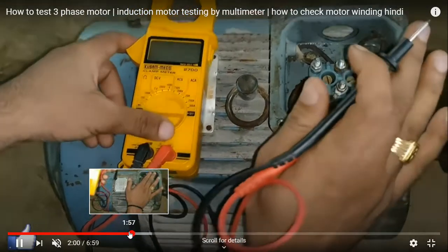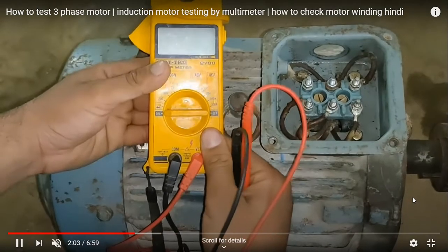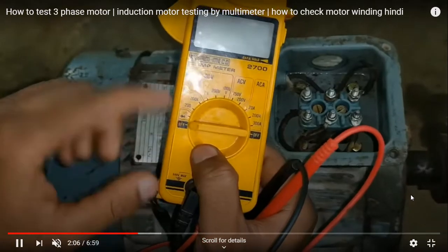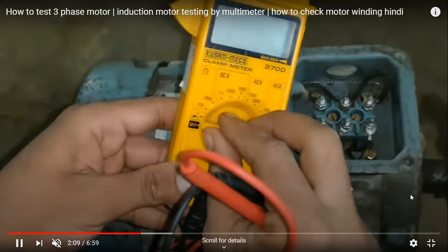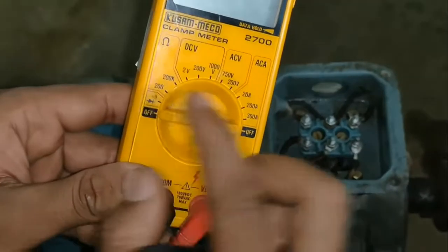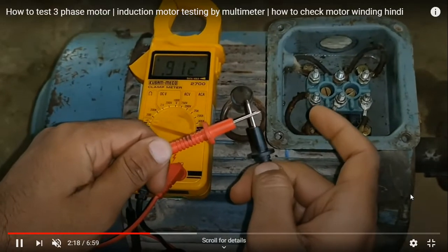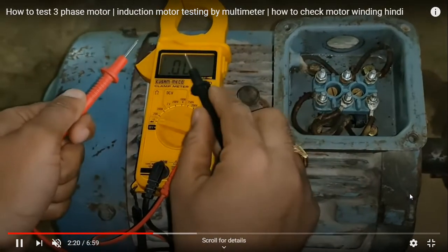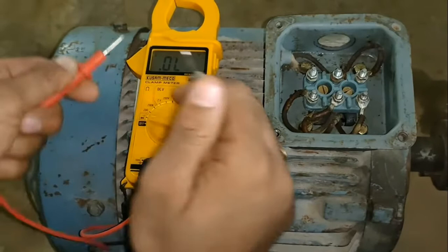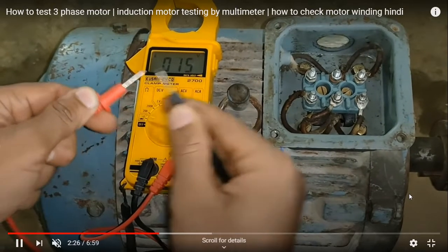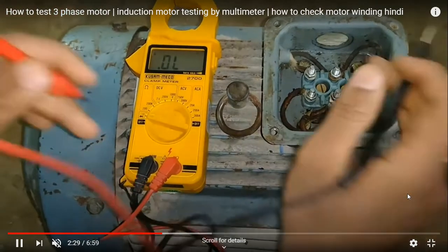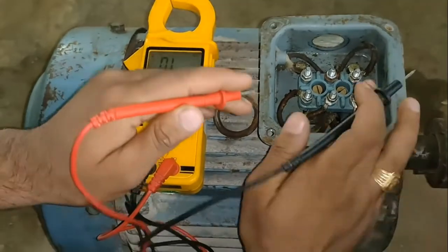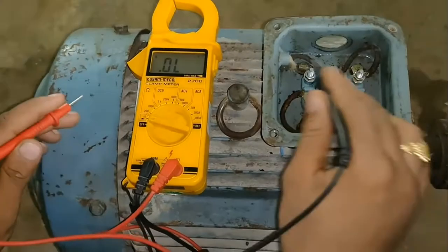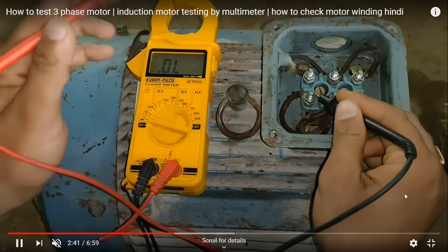So obviously you have a clamp meter. This is the use of clamp meter by which you can check the windings. As you can see, there is a beep sound included for testing, so you can test whether your device is working well. This is testing before you actually test the motor. So for checking the winding, this sort of test is very much useful.